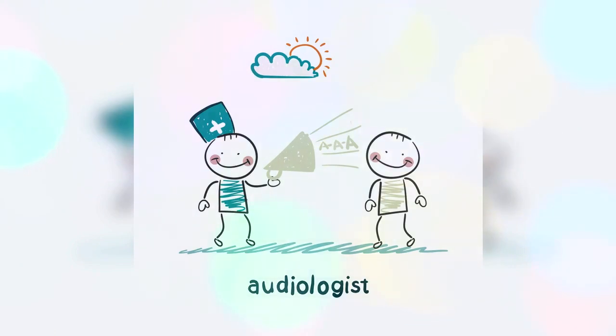Behind the ear, BTE, hearing aids. All electronic components are housed inside a housing that will rest on the ear. By the elbow at its end, it is attached to the mold using a flexible plastic tube. They are the only ones suitable to cover hearing impairments from slight to deep, being necessary for these last ones apparatuses of greater size. This is due to the necessity to incorporate a more powerful earpiece. The main advantages of this apparatus are its power, its easy manipulation and the possibility of adapting the FM, frequency modulated, system. It allows the direct transmission of the sound from a transmitter source, for example, a microphone. Its main disadvantage is that it is perhaps the least discreet.